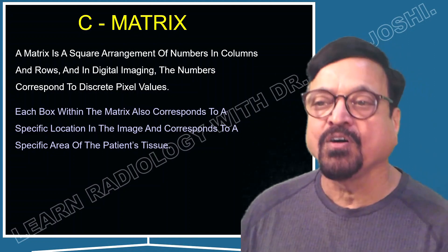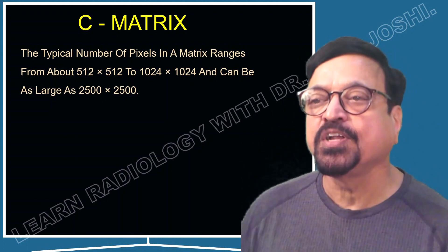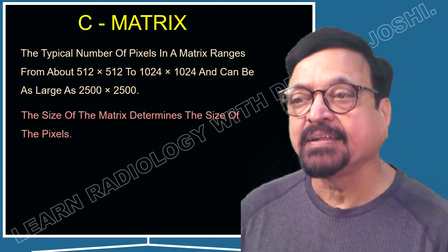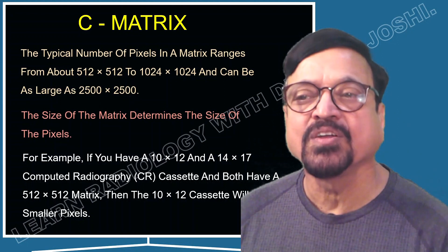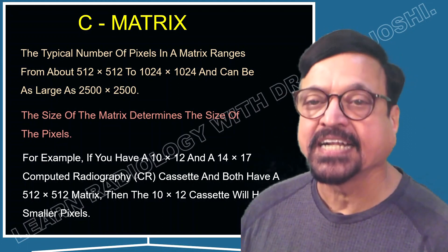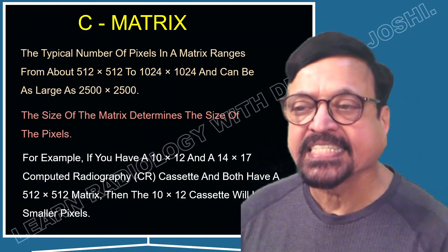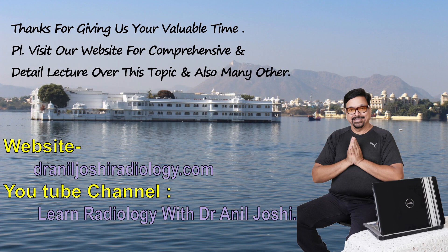In digital imaging, the numbers correspond to discrete pixel values. Each box within the matrix corresponds to a specific location in the image and to a specific area of the patient's tissue. The image is digitized by both position — spatial location — and intensity — gray level. The typical number of pixels in a matrix ranges from 512×512 to 1024×1024, and can be as large as 2500×2500. The size of the matrix determines the size of the pixel. For example, if you have a 10×12 and a 14×17 computed radiographic cassette, both with a 512×512 matrix, then the 10×12 cassette will have the smaller pixel size.